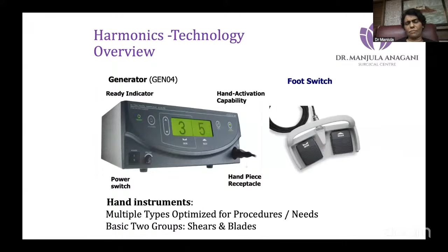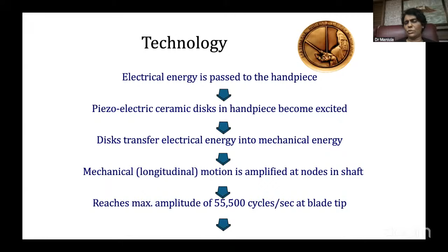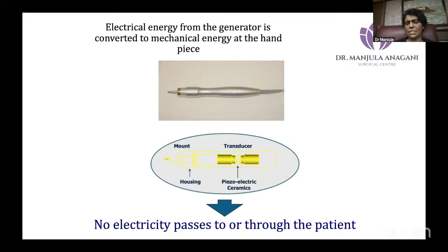This is the way. The original generator was Gen 04. Now we have Gen 11, then we have the advanced bipolar, both the Enseal and the generator. So what we are looking at is electrical energy, which is coming to a piezoelectric ceramic disc, then transferring the electrical energy into mechanical energy, where 55,500 cycles will come per second at the blade tip. So this is how the electricity will not pass through the patient.